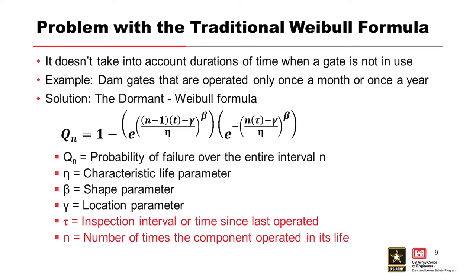So, the traditional Weibull formula doesn't work very well for those types of exercise schedules. So, the dormant Weibull formula was developed. A couple more parameters were added for the dormant Weibull formula. Those bottom two in red, the inspection interval or time since last operated.